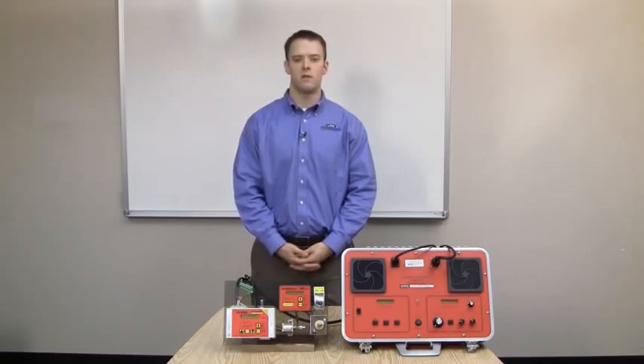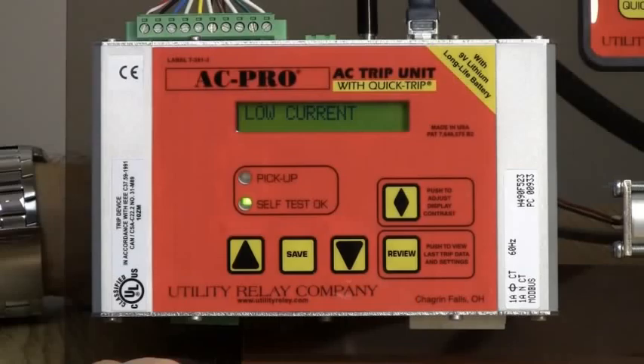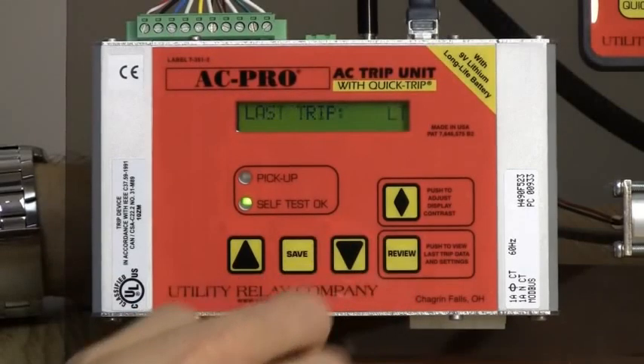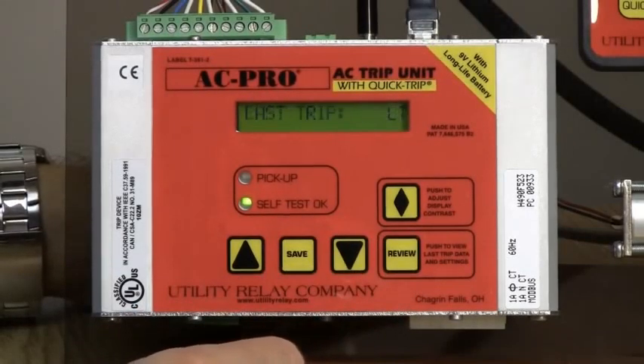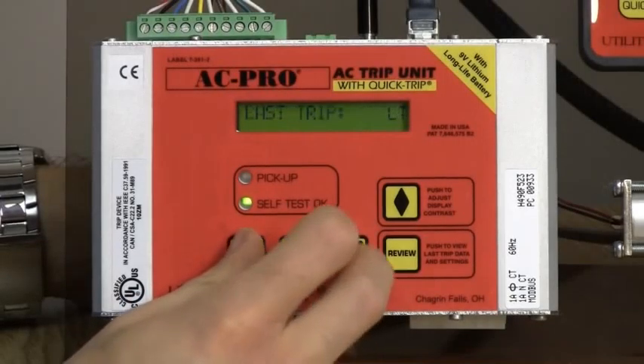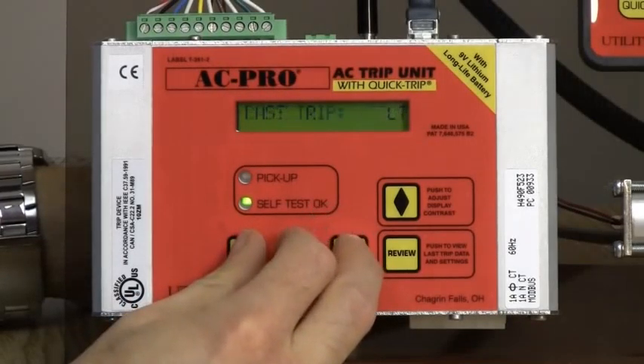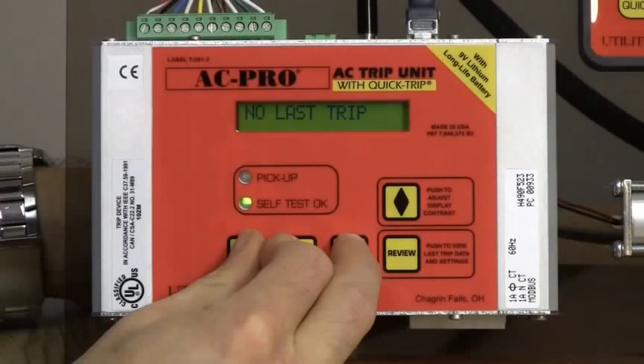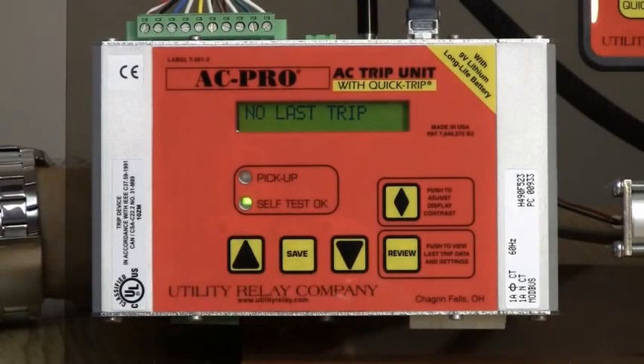Clearing the last trip data is very easy. I will push the review button so the last trip data is displayed. While the last trip data is displayed, push both the up and down buttons. With these 2 buttons pushed, push the enter button. Then release all 3 buttons. The last trip data and trip counter is now erased, and the AC Pro should be displaying no last trip.